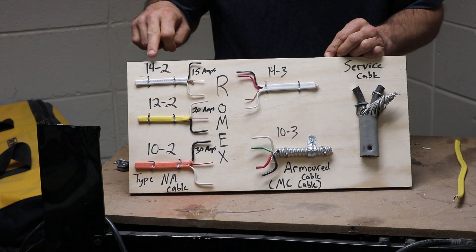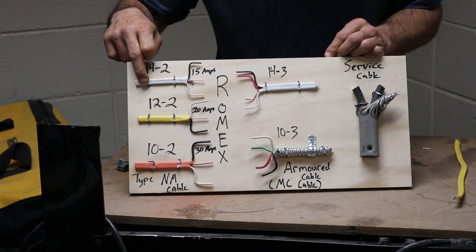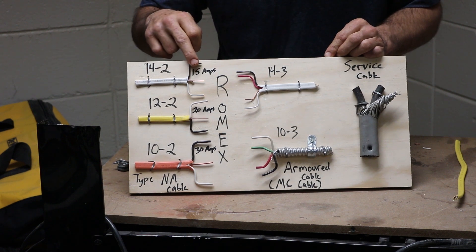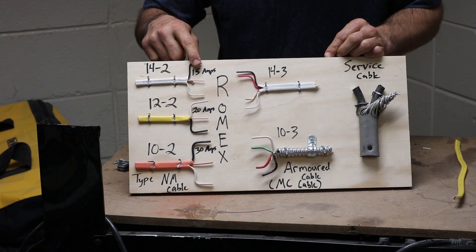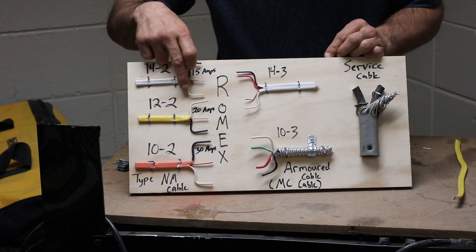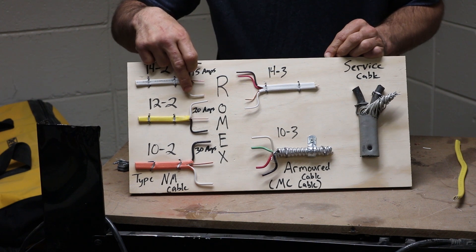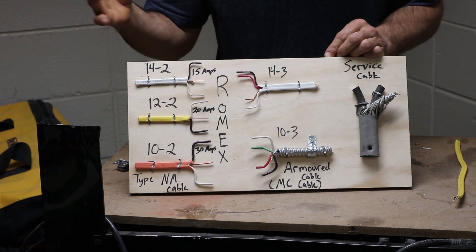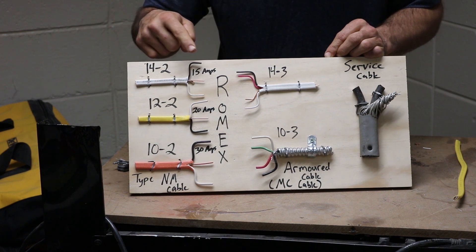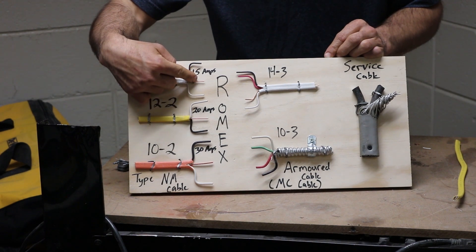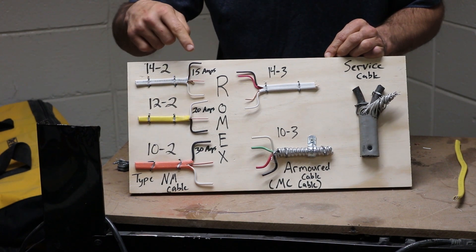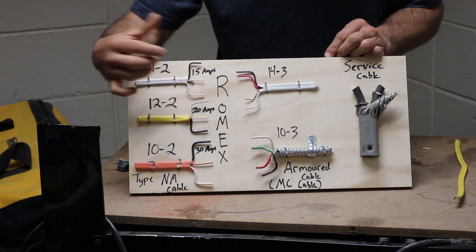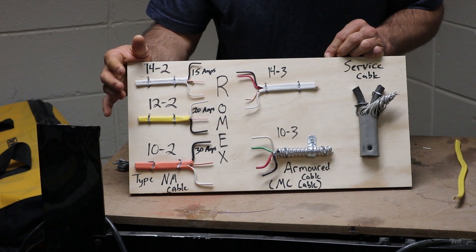If you notice right here, I wrote 14-2. 14-2 means it's 14 gauge wire and there are two conductors, so you have a black and a white. Your black is your current carrying conductor, and then the white is your grounded conductor. And then you have your grounding conductor, which is also known as the ground. In the field, this would be your hot, this would be your neutral, that would be your ground. NEC code: current carrying conductor, grounded conductor, grounding conductor. So that can get somewhat confusing there.